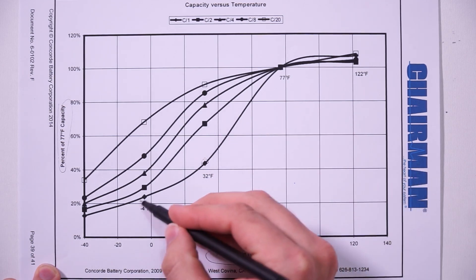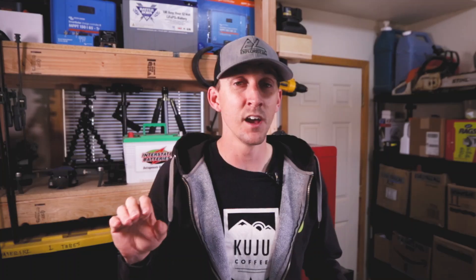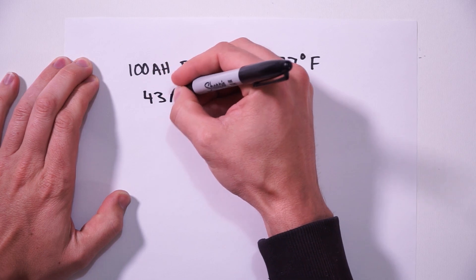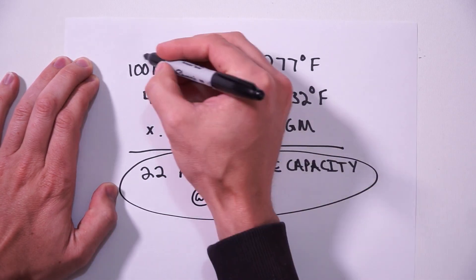Now let's talk about the exact same idea but with AGM. I couldn't find a nice third-party graph from a scientific journal, but this graph is from Concorde Battery Corporation. This graph shows the percent capacity in relation to degrees Fahrenheit. In order to compare apples to apples, we need to be looking at the line with the diamond on it, as it's the same discharge rate we were looking at on the lithium graph. Jumping down to freezing — 32 degrees — we can see that battery capacity has dropped to about 43%. AGM batteries don't like to be discharged below 50% of their max capacity, as doing so greatly shortens their lifespan. So we've got a 100 amp hour battery at 32 degrees, which is now effectively a 43 amp hour battery, and we can really only use 50% of that capacity — meaning our 100 amp hour AGM battery is operating on about 22 amp hours.